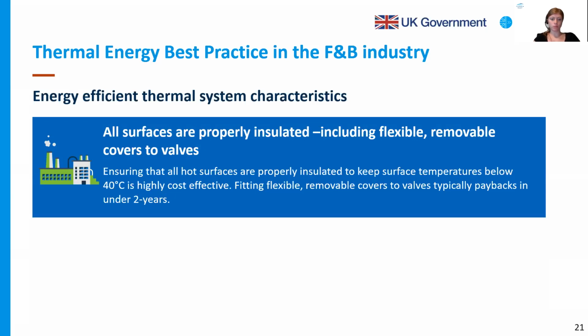This is not only an energy saving procedure, but also a safety aspect, because especially for boilers, when you have boiler operators working around the systems, especially operators moving around the steam networks, it's also very important to ensure that there is no venting steam or poorly functioning insulation, such that hotspots develop on the steam network beyond 40 degrees. So that's also a safety hazard. So it's killing two birds with one stone. So as much as we have safety culture in a plant, it's also critical to have energy culture. Yeah. Next slide.